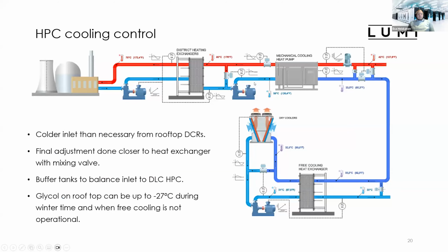This HPC cooling control, this is an overview diagram of our HPC cooling. So basically this is outlet from the Lumi CDUs, which is approximately 42 degrees on the production. We can use the mechanical cooling and then put the 32 degree into the Lumi, or we can run it in the partial free cooling when we are using in series first heat pump and then free cooling heat exchanger, or we can bypass the heat pump and use only free cooling.